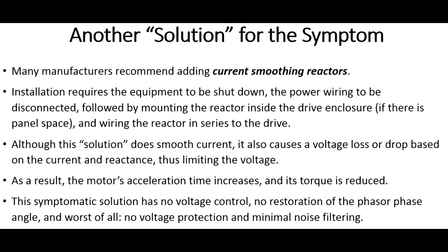So though it actually does smooth the current a bit, it does have a voltage drop across it. A voltage drop in series with your drive causes the voltage to be lower at the input terminals on the drive. So that voltage can go up and down based on current, and that can cause some unrepeatability in your process. It can also cause a lower amount of torque and longer acceleration on the motor that the drive is powering. So the line reactors do not address a voltage balance.